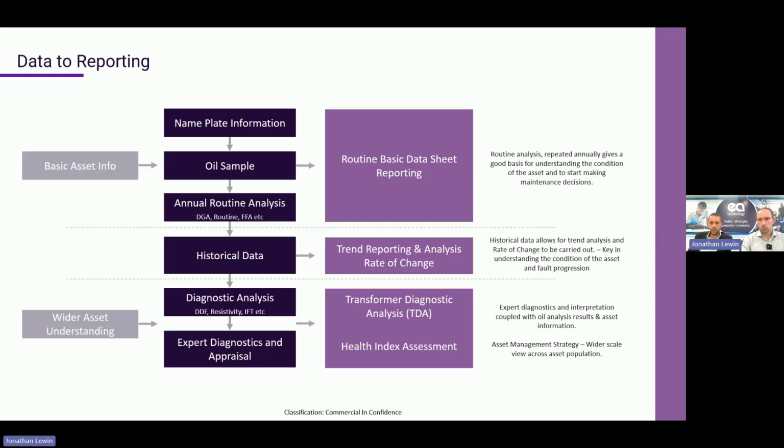You can also do a full health index assessment, which we'll come on to in the next section. That's taking not just the history, not just the fluid based on lab results, but also the asset age and other data to predict where the asset's end of life is.